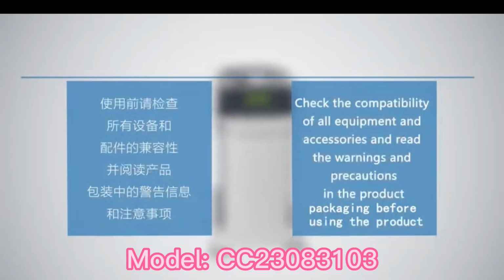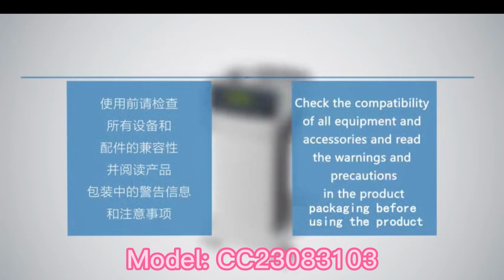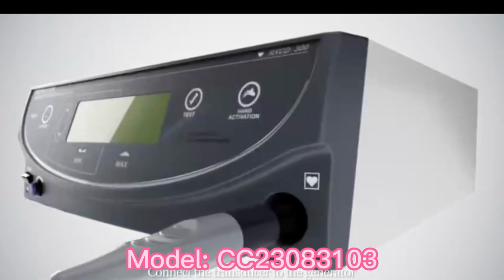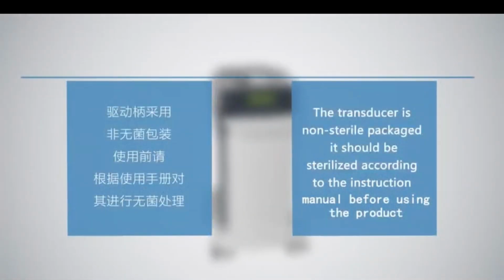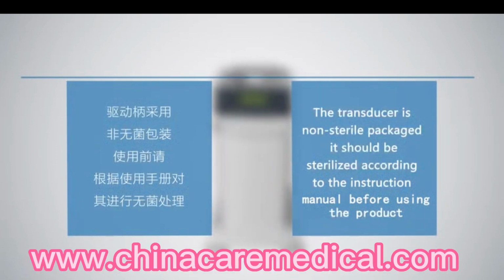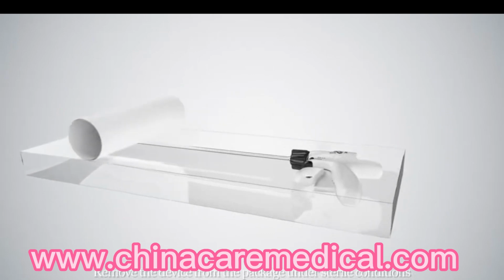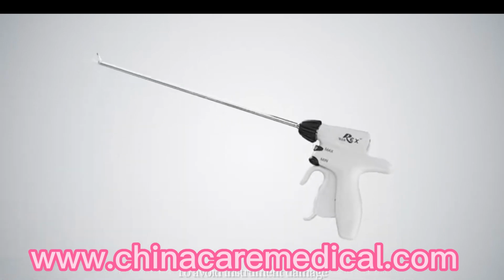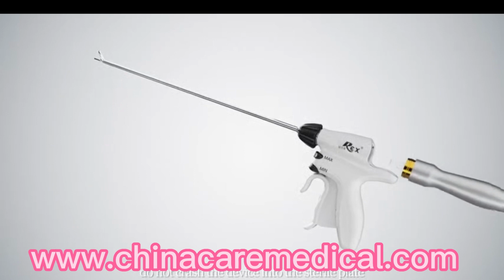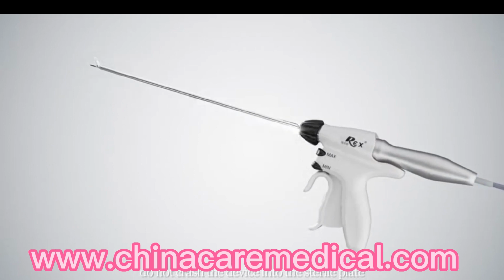And accessories, and read the warnings and precautions in the product packaging before using the product. Connect the transducer to the generator. The transducer is non-sterile packaged, so it should be sterilized according to the instruction manual before using the product. Remove the device from the package under sterile conditions. To avoid instrument damage, do not crash the device into the sterile plate.